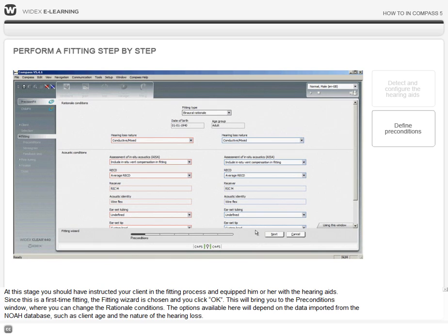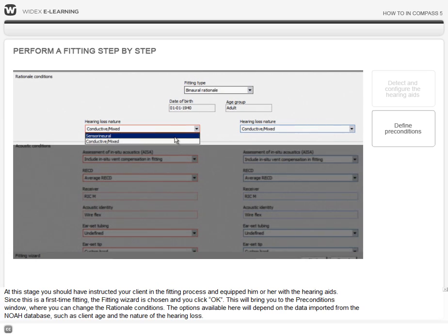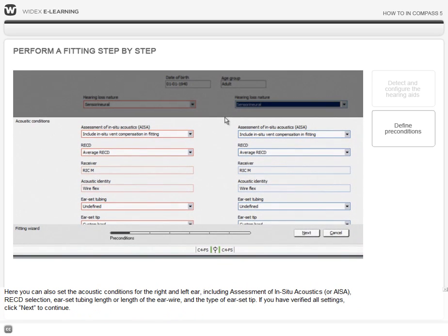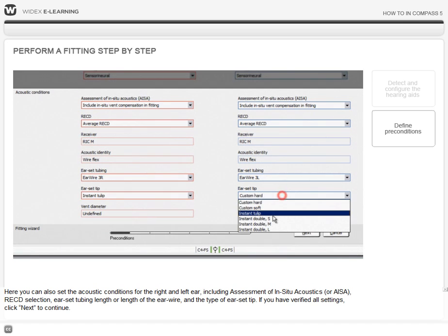This will bring you to the Preconditions window, where you can change the rationale conditions. The options available here will depend on the data imported from the NOAH database, such as client age and the nature of the hearing loss. Here you can also set the acoustic conditions for the right and left ear, including assessment of in-situ acoustics or AISA, RECD selection, ear set tubing length or length of the ear wire, and the type of ear set tip. If you have verified all settings, click Next to continue.